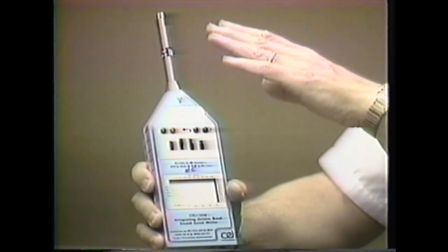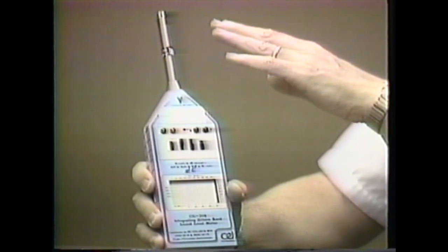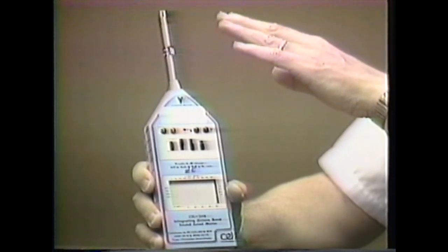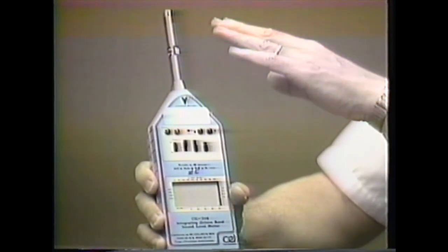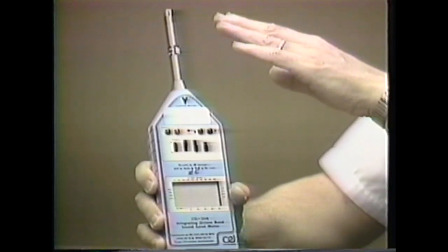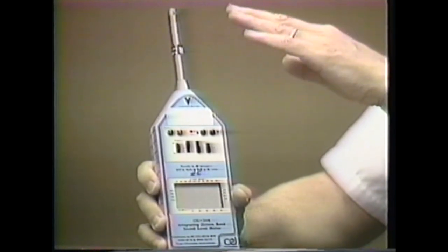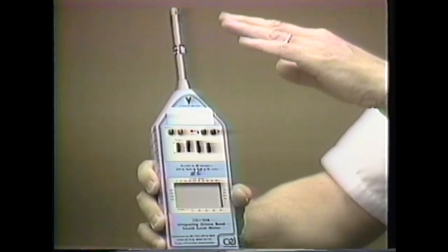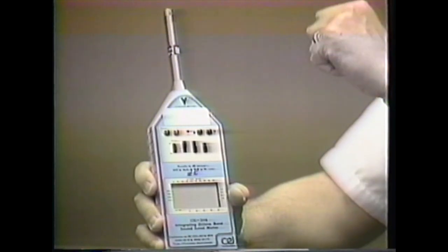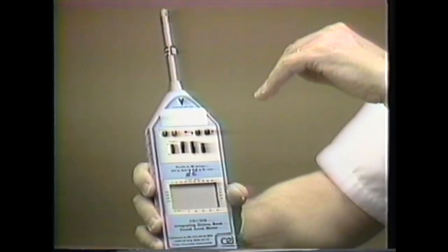The microphone is sensitive to bumping type of damage. The microphone is sensitive to wind error. The microphone can be damped by moisture condensation, so accumulation of moisture would be unacceptable. The microphone can be interfered with by dust. The microphone can be interfered with by electromagnetic fields. So anytime you think you have one of these problems, if you're uncertain as to what's best to deal with them, please contact your supervisor. One way of dealing with the wind effects is to use a wind screen.